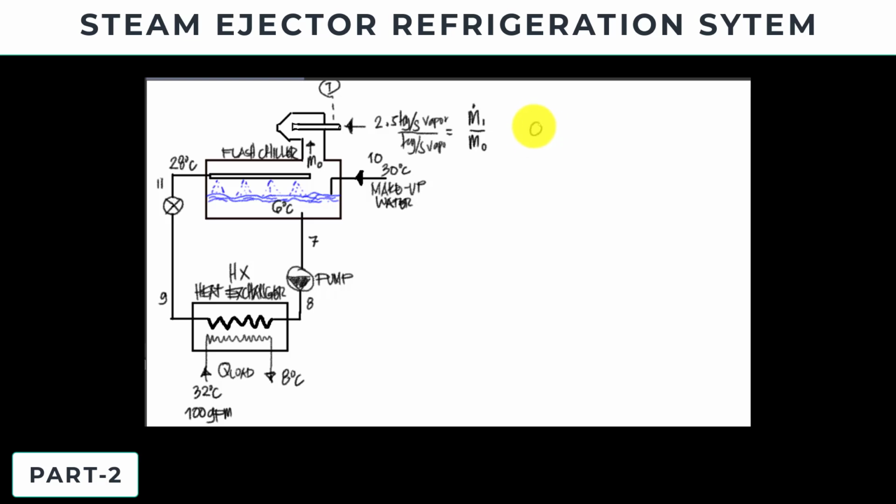So for my Q load, solving for my Q at load, this is equal to the mass flow rate of the load. I'm going to give the subscript ml to identify that this is a load. Now this is the specific heat of H2O times the change in temperature. You will notice here we are only using sensible heat. We are not freezing the water, since the load of the system is usually purely water, and it must be circulated back and forth.